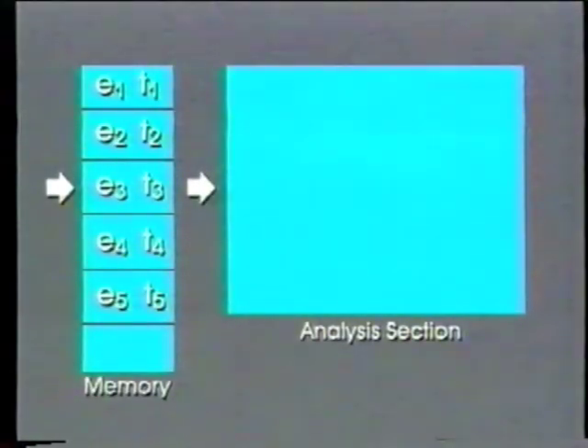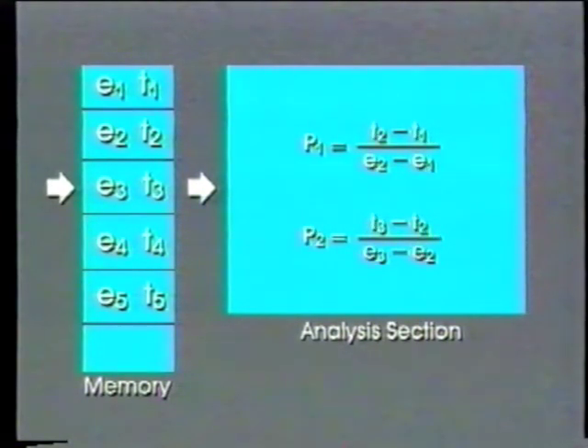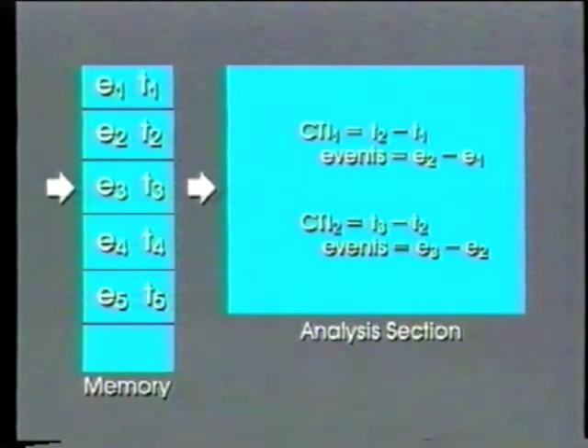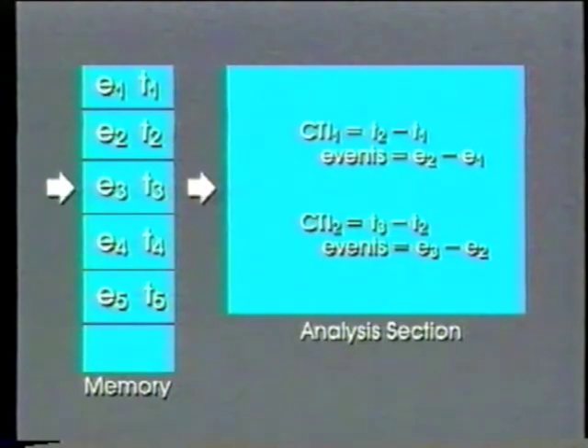The 5371 can analyze data in a variety of ways: a series of frequency measurements — events divided by time — period measurements — time divided by events — or continuous time interval measurements, where time and events are displayed separately. In each case, the internal hardware counts events and time in the same way, but the results are calculated differently.